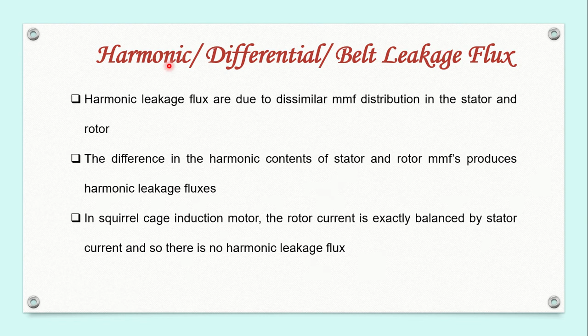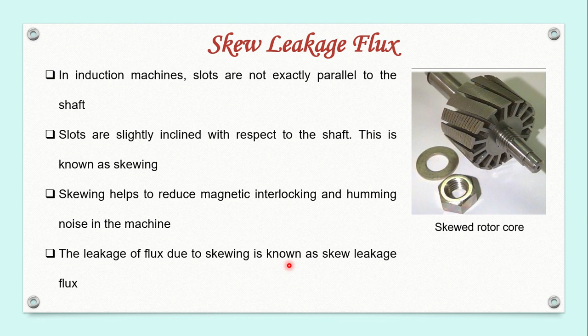So next type is the skew leakage flux. You have heard of this term skewing. The rotor of an induction machine is shown here. In induction machines, the rotor slots are not exactly parallel to the shaft. They are slightly inclined with respect to the shaft. This is known as skewing of the rotor. Skewing is done to reduce magnetic interlocking and magnetic humming noise. Due to skewing, the total flux produced in the stator will not link with the rotor. So there is a difference between the total flux and the flux linking with the rotor, and this flux is known as the skew leakage flux. Or simply, the flux that is lost due to skewing is known as skew leakage flux.